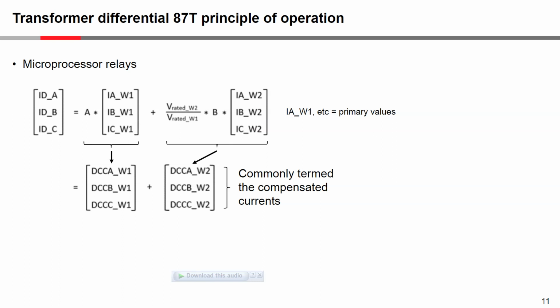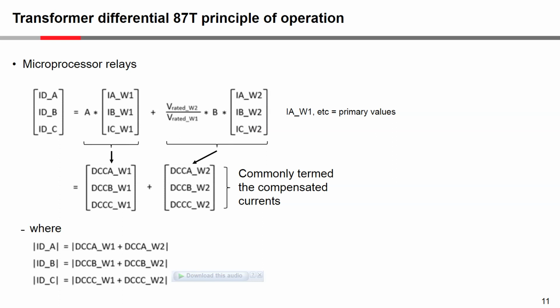And this is how you would then get the differential current. If you're looking at the differential current for phase A, it would be the IDCCA winding 1 plus IDCCA winding 2. And for phase B and phase C, it would be similar: winding 1 plus winding 2 for B phase, and winding 1 plus winding 2 for C phase.